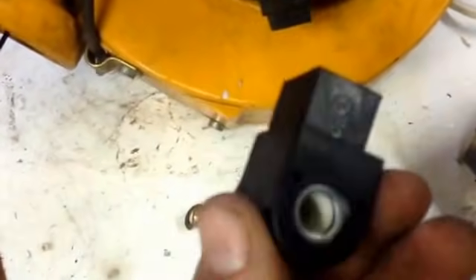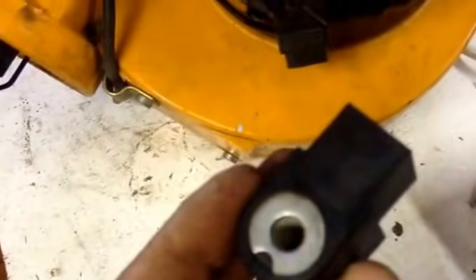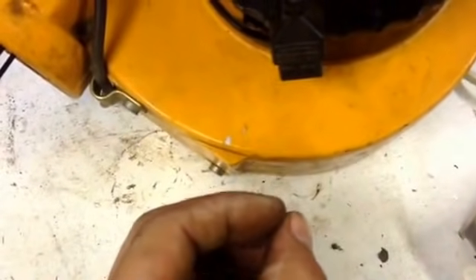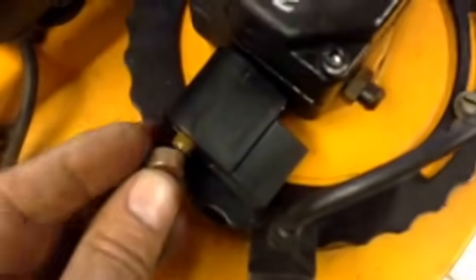Now what happens is the little fine coils of wire in here, when it's been running for 4, 5, 10, 20 minutes, will heat up, and if there's a break in them, the expansion of the heat will just open it, and it will stop contacting, it'll lose magnetism, and off it goes. That's a common one. So they're pretty easy to tell, but the usual fault is it runs for 10 minutes, then shuts off, and if you leave it for 5 minutes, it'll restart perfectly fine and go again. Annoying.